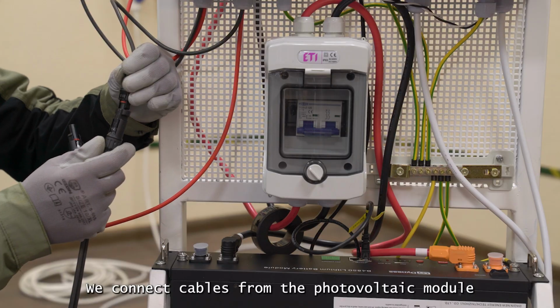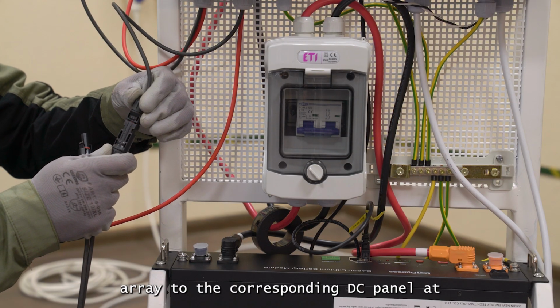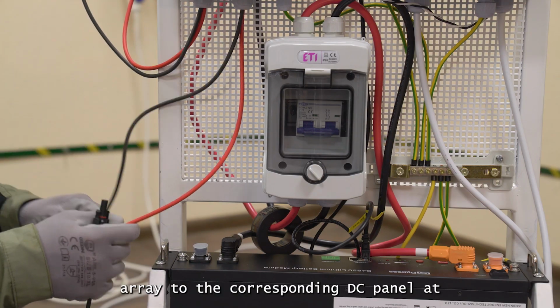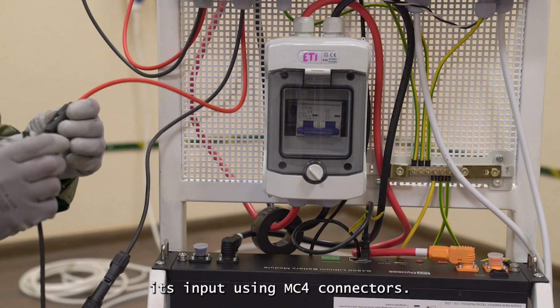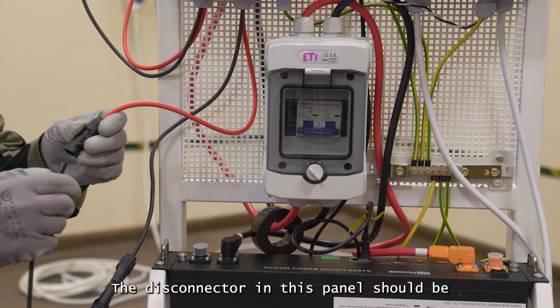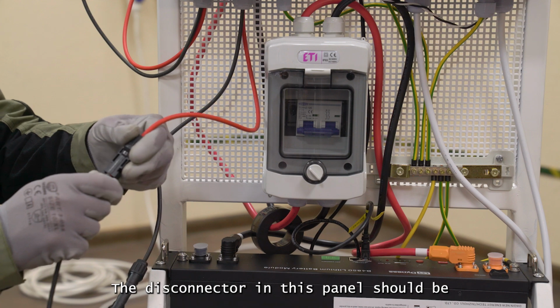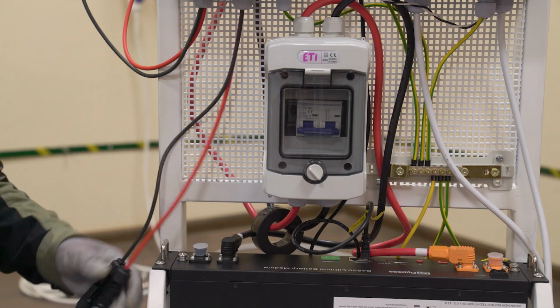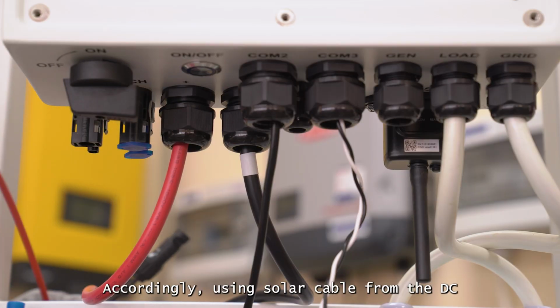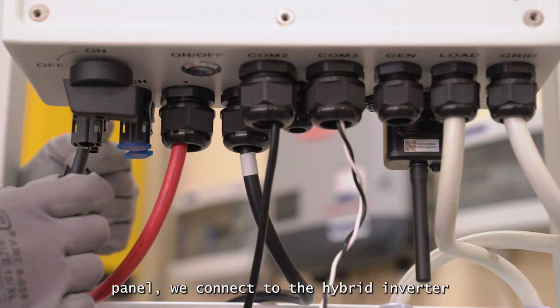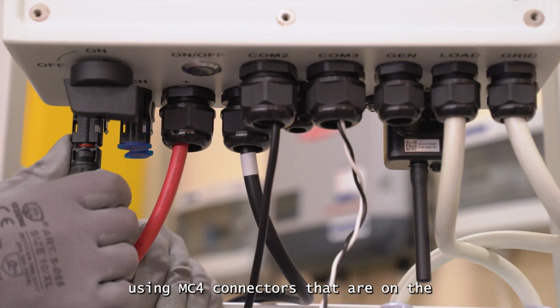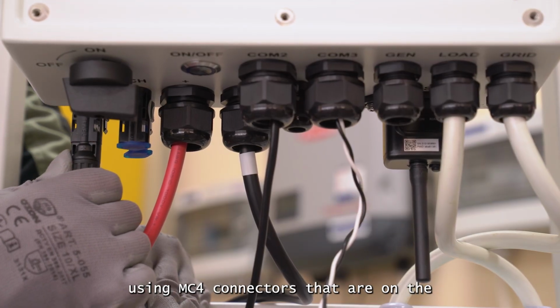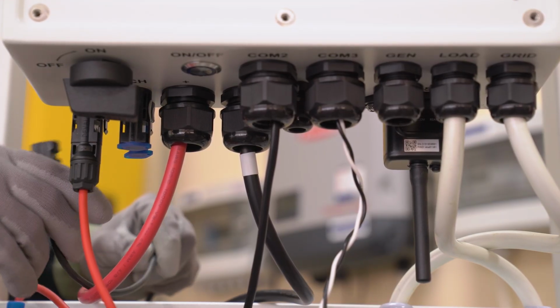We connect cables from the photovoltaic module array to the corresponding DC panel at its input using MC4 connectors. The disconnector in this panel should be in the off position. Accordingly, using solar cable from the DC panel, we connect to the hybrid inverter using MC4 connectors that are on the solar cable and grid inverter.